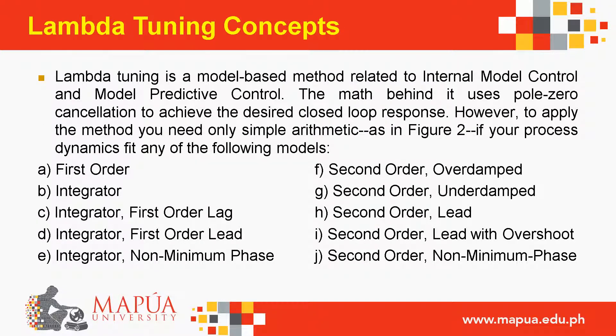Lambda tuning is a model-based method related to internal model control and model predictive control. The math uses pole-zero cancellation to achieve the desired closed loop response. To apply it, you need only simple arithmetic. Process models supported include: (A) first order, (B) integrator, (C) integrator first-order lag, (D) integrator first-order lead, (E) integrator non-minimum phase, (F) second-order overdamped, (G) second-order underdamped, (H) second-order lead, (I) second-order lead with overshoot, and (J) second-order non-minimum phase.